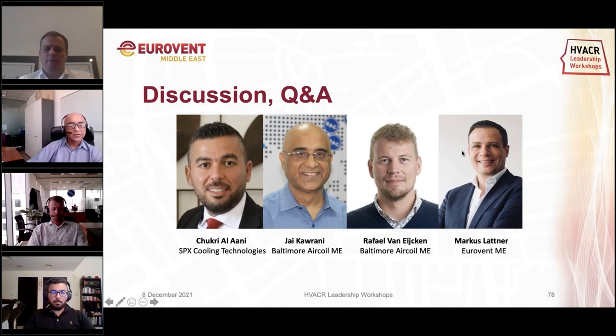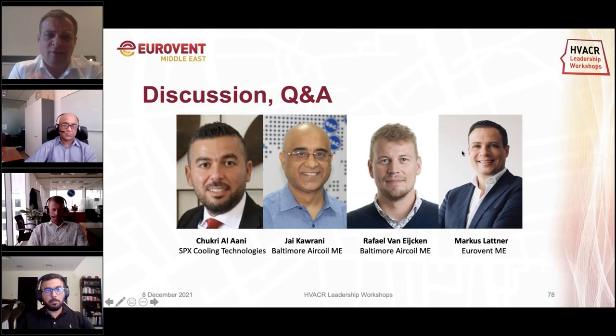It is really essential to not just look at a label or a logo. As Jay rightly said, stating you're a member of Eurovent or CTI doesn't mean your product is certified. The performance certificate is an essential document to look at, because it gives you an overview of which parameters are certified, what the rated capacity is, and how the performance is doing. All the parameters are outlined in the certificate. So always cross-check the validity of the certificate with the online database, and of course also look at the details of the certification sheets.